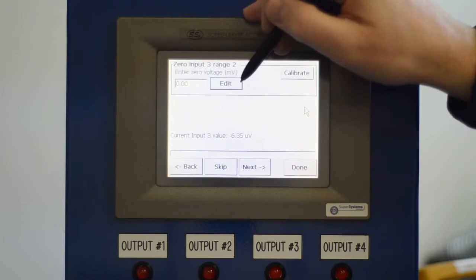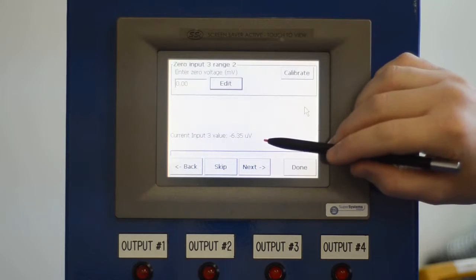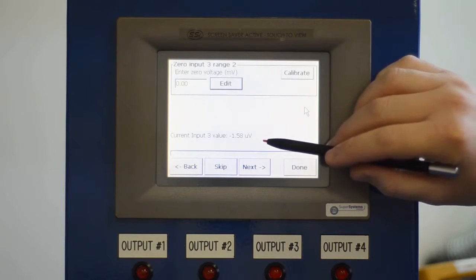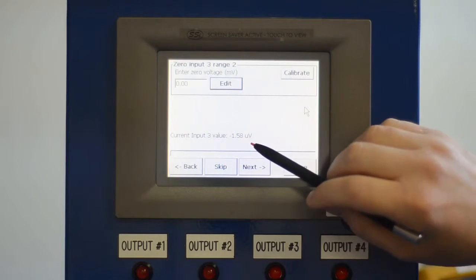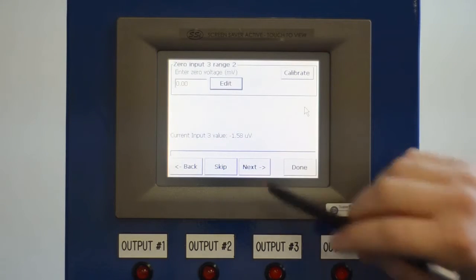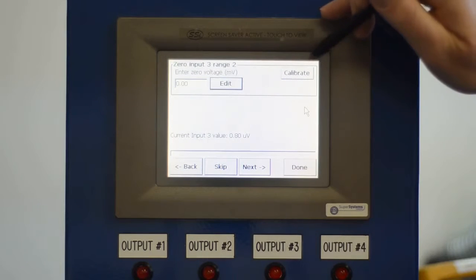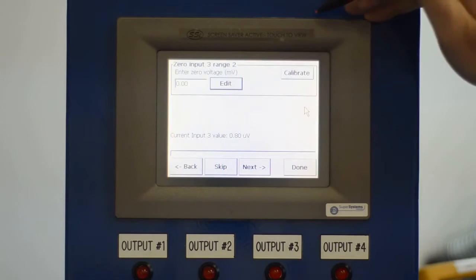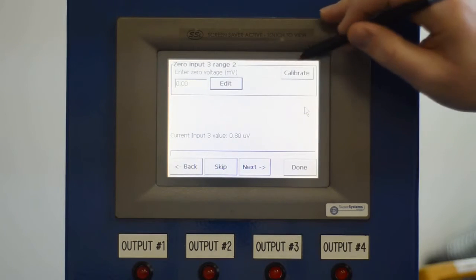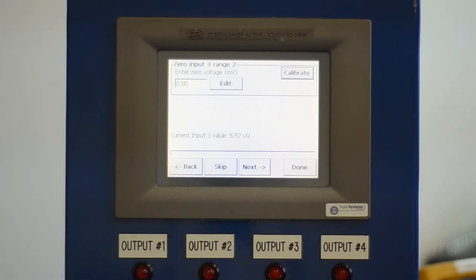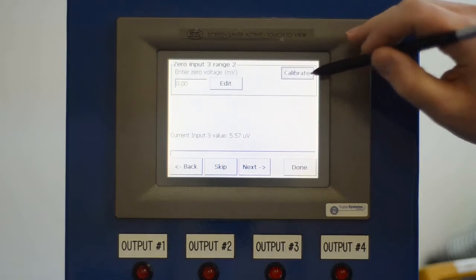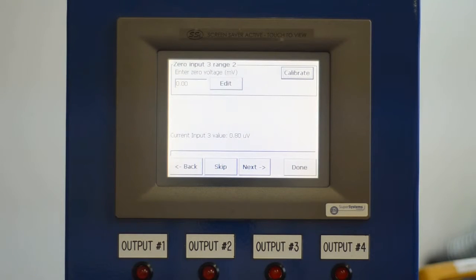So we're sourcing in 0 millivolts, and then this value down here tells us in a microvolt reading what it's actually seeing on that current input 3. Right now it's seeing a negative 1.58 microvolt. We'll give it a second to zero out there, and as you can see now it's holding pretty steady. We're going to select calibrate. As you can see, it took a second there, but the progress meter towards the bottom of the screen is now calibrating the input for 0.